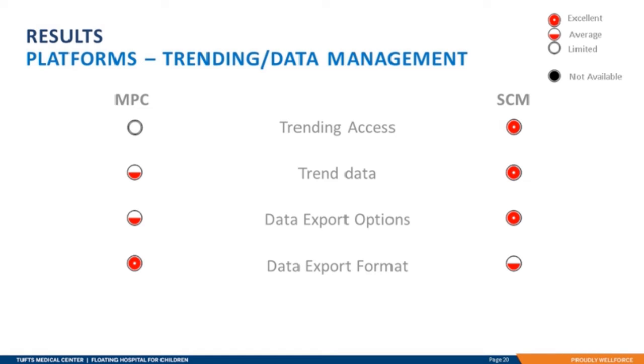Finally, on the discussion of features, we look at trending and data management. As mentioned earlier, while both platforms have trending capabilities, the trending in Machine Performance Check is not very user-friendly. The multiple trending options in SunCHECK Machine give the user a lot of flexibility in accessing the data. The ability to see comments on the trend line is very beneficial, so that notes on outliers can be easily accessed without a lot of investigation work. SunCHECK Machine also has multiple export options, so you can export a single test or a whole trend line. Machine Performance Check will batch export, and you need to go through multiple folders to access the correct test. That being said, the organization of the data for Machine Performance Check export is slightly better than SunCHECK Machine.